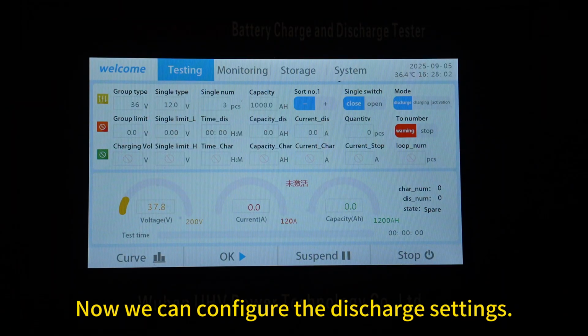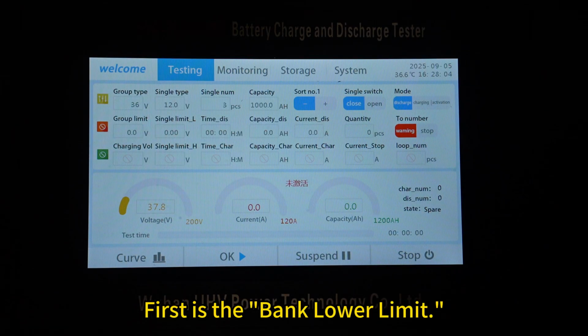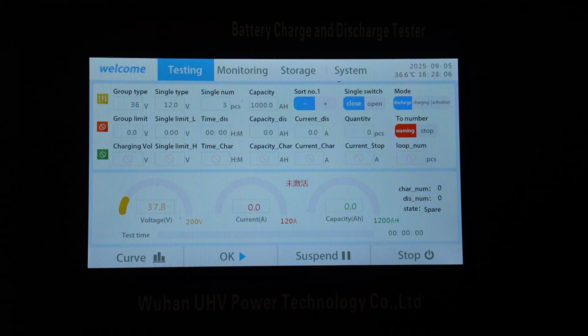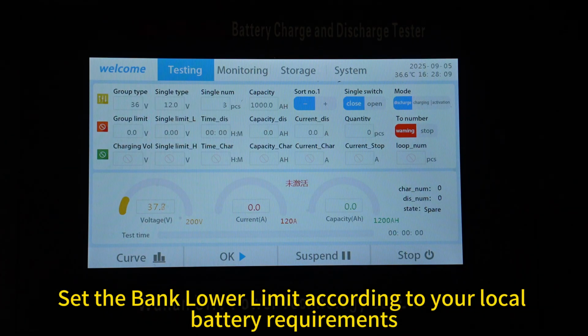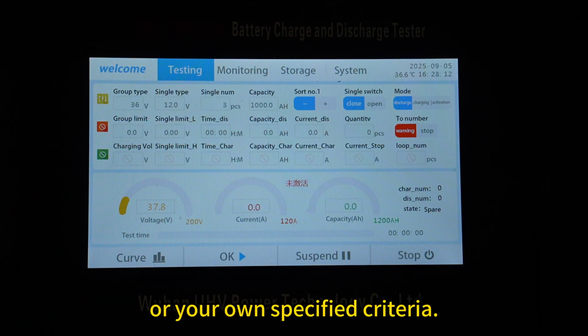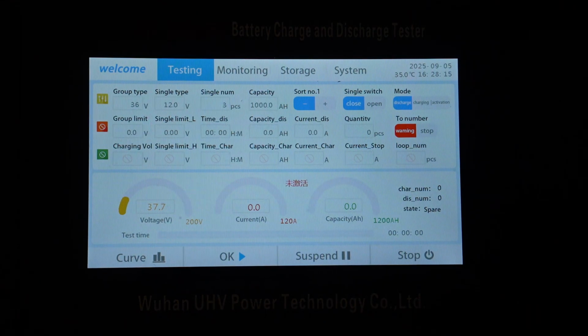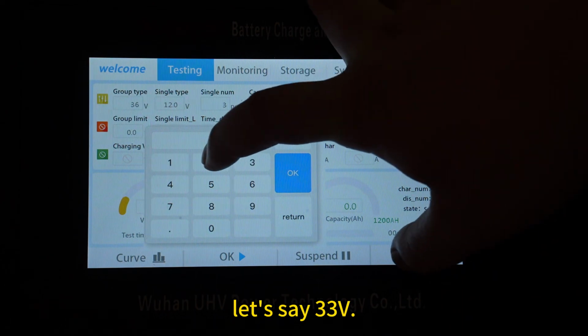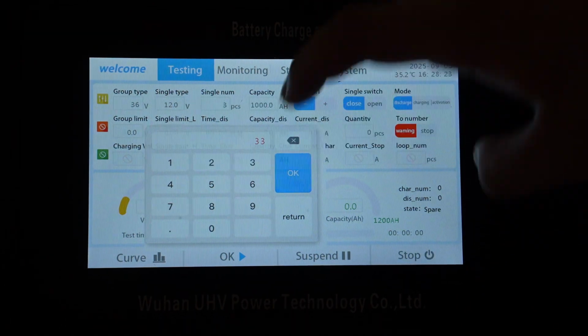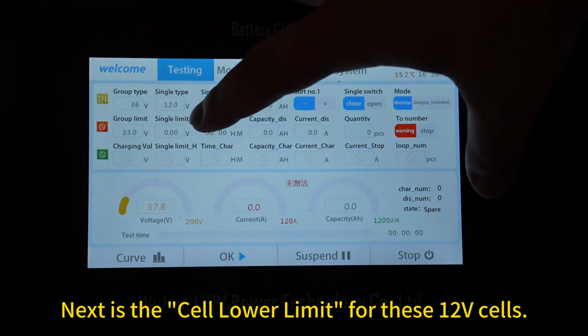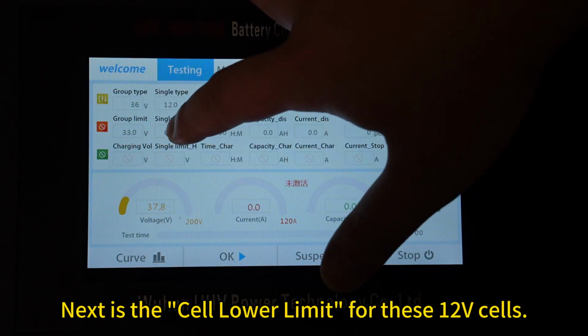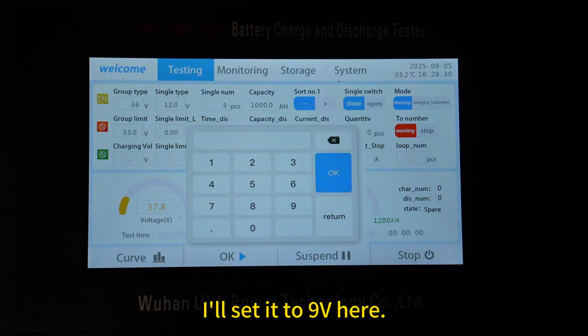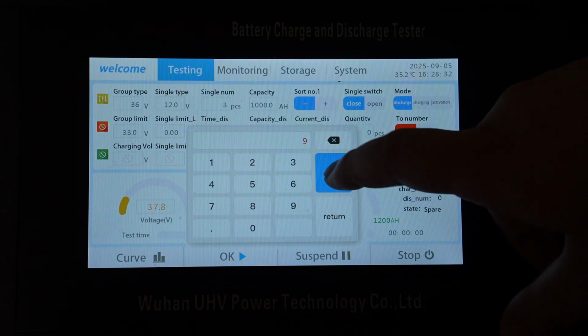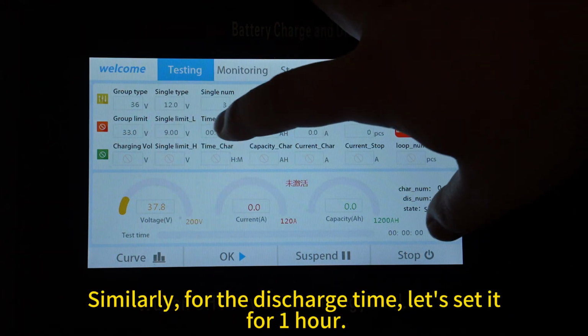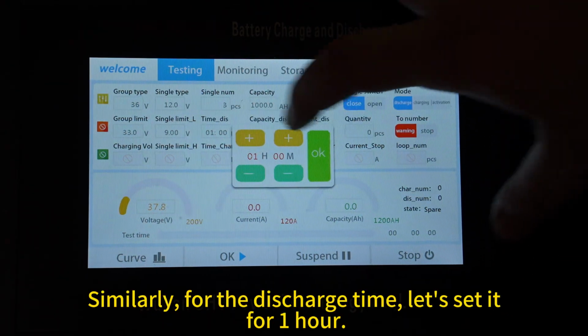Now we can configure the discharge settings. First is the bank lower limit. Set the bank lower limit according to your local battery requirements or your own specified criteria. For this demo, I'll set it arbitrarily, let's say 33 volts. Next is the cell lower limit for these 12 volt cells. I'll set it to 9 volts here. Similarly, for the discharge time, let's set it for 1 hour.